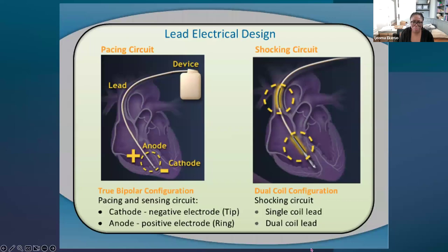This is just an example of the lead electrical design where your sensing or pacing circuit is typically around your anode and cathode, near the tip of the lead. It's either smaller, if you have a dedicated bipolar, or if you have an integrated bipolar, your sensing circuit is a little bit wider.